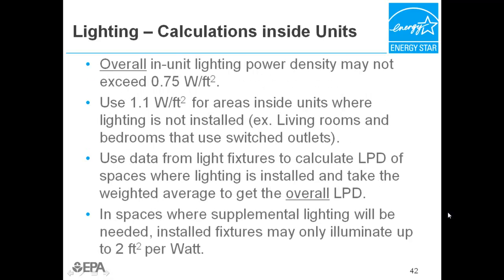As mentioned previously, overall in-unit lighting power density may not exceed 0.75 watts per square foot. For example, bathrooms can have higher lighting power densities if other spaces inside the unit can compensate for it while still providing enough illumination. To calculate the overall lighting power density inside a unit, use 1.1 watts per square foot for areas inside units where lighting is not installed, such as living rooms and bedrooms that use switched outlets. Use data from light fixtures to calculate lighting power density of spaces where lighting is installed, and then take the weighted average to get the overall lighting power density.